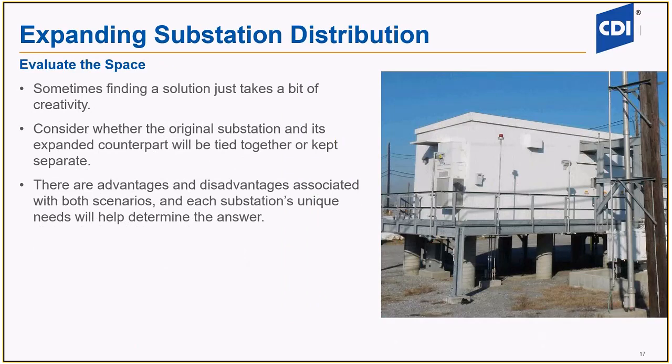Knowing the ampacity and voltage levels, now consider where on site you can locate your new gear. You need to plan for how you expect the utility power to get onto your site. You want to keep your substation or switchyard out of any hazardous area, and ideally you'd like to locate it close to where you are planning for the new loads to be, so you won't incur additional costs for perhaps longer cable runs or infrastructure to hold the cables.